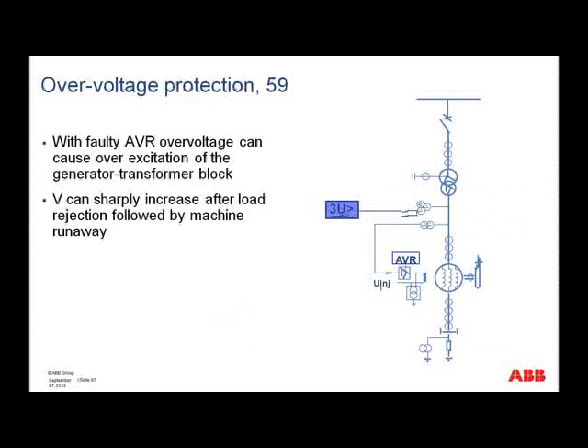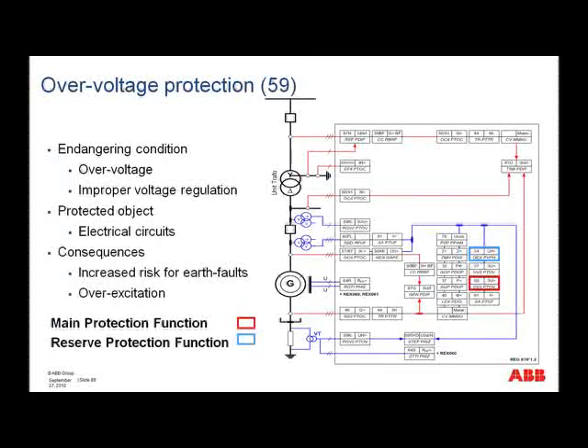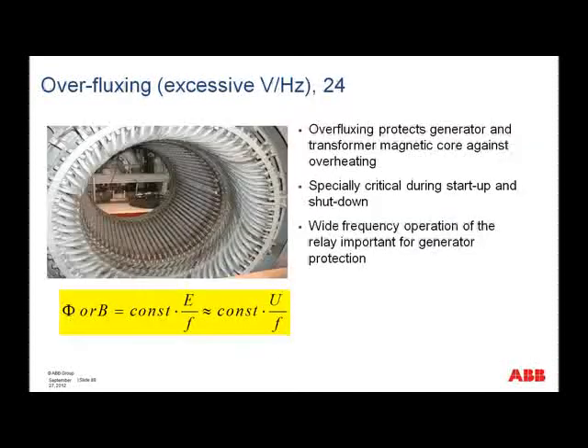Over voltage protection or over voltages, this can come, of course, from a faulty AVR. It can come from a sharp increase in the voltage because of load rejection followed by some machine runaway. And so you can see in this picture we have the over voltage protection, that's phase over voltage. And also as a reserve function we have the over excitation, because this is also working on there being an over voltage.